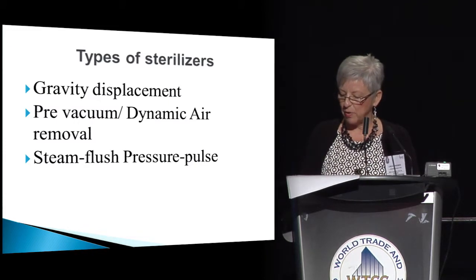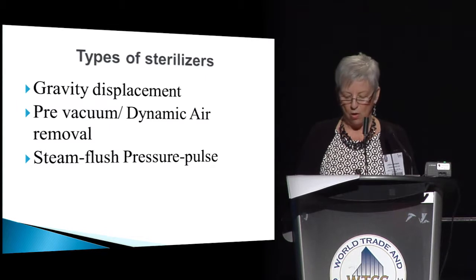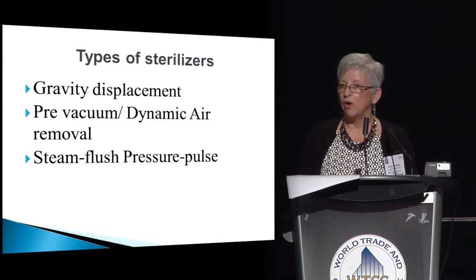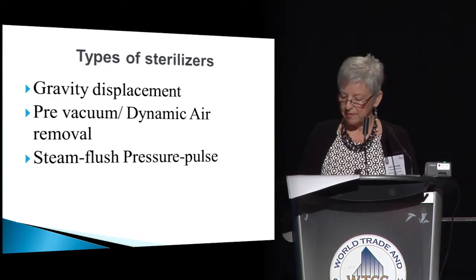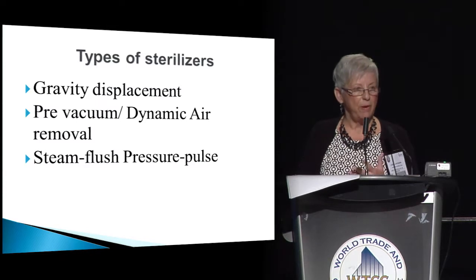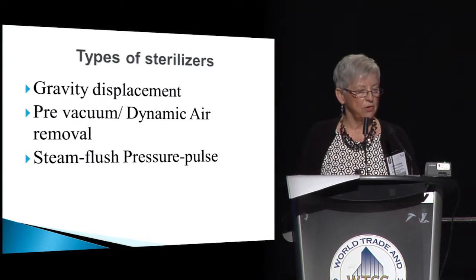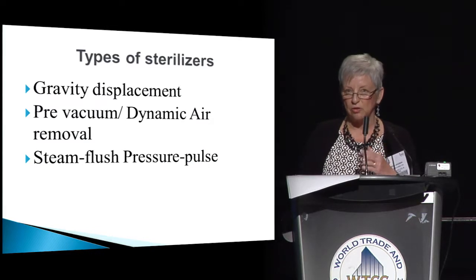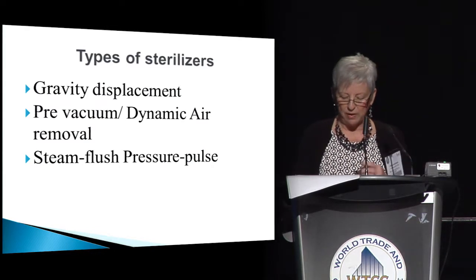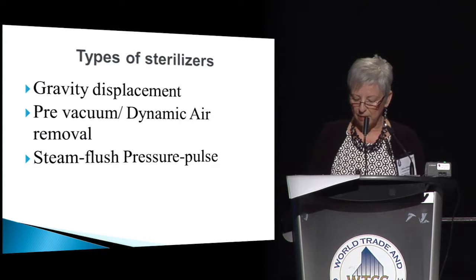If any air is present, it causes cold spots or air pockets that will prevent the contact of the sterilant to the devices. This will cause wet packs and sterilization failures. So gravity sterilizers are really, really sensitive to how they are loaded, and I'll talk a little bit about loading in a few slides ahead.